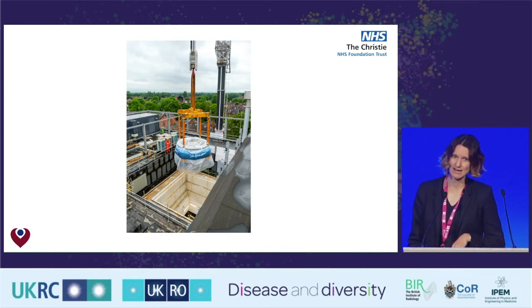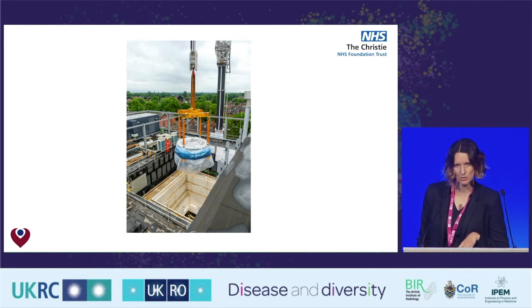So I showed you UCL cyclotron being delivered. And you might have thought, well, why is it being delivered now if they're not opening until 2020? They're delivering it, they're 30 metres underground, and then they'll build 5 stories above. Whereas the Christie were built, I should get the tense right, above ground, because we sit on bedrock. So we built above ground, and then in simple terms, like you can see on this picture, we left the roof off, and we just carefully lowered the equipment through the roof. So you can see the cyclotron, but the gantries went in the same way. And if we need to take them out in 20 years' time, that's how they'll come out.